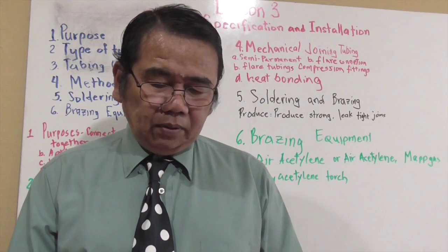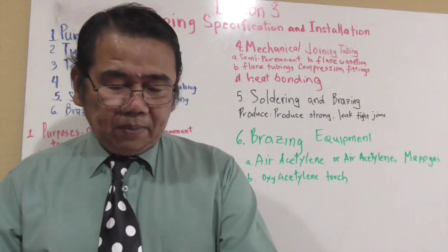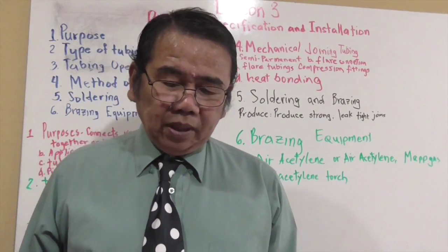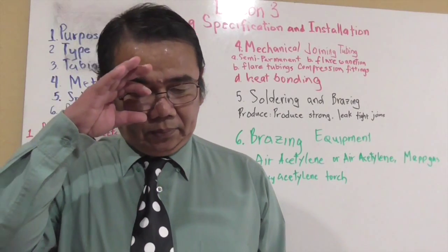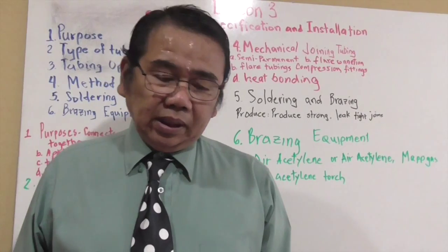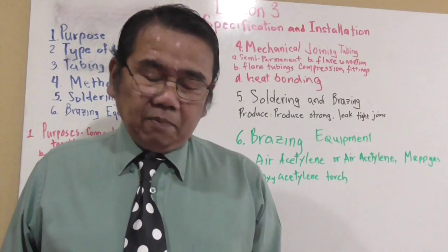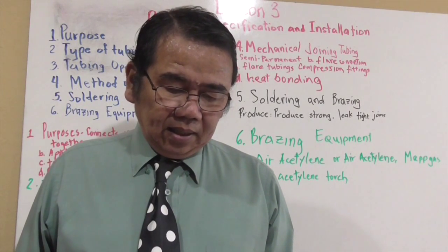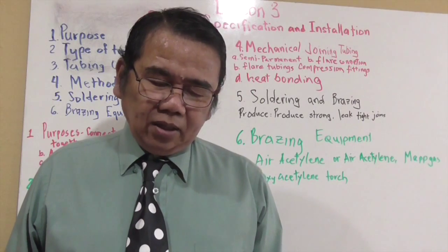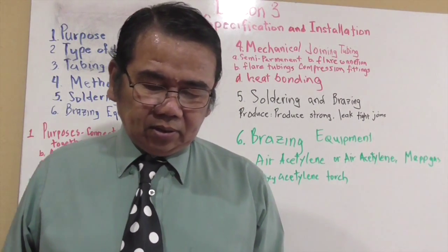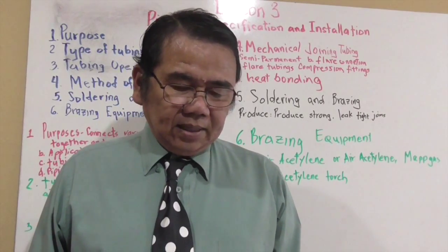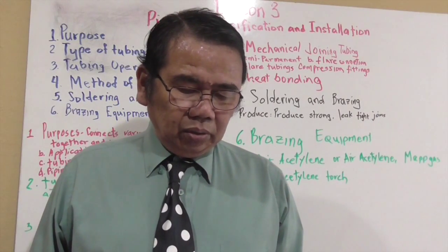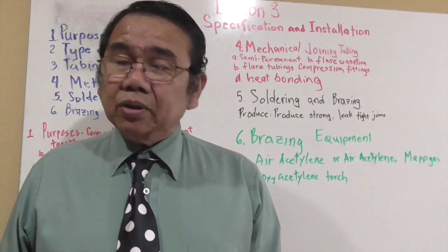We're going to continue with mechanical couplings. Now we're going to talk about flared fittings. Flared fittings are needed to accommodate many types of flared tubing, such as various elbows, tees, and unions. Flare nuts are SAE, Society of Automotive Engineers, pipe threads. Some fittings such as flare hub unions are made to join to national pipe threads.